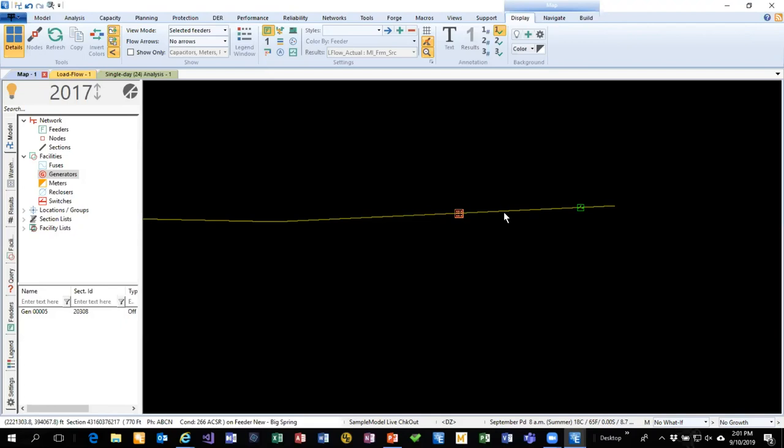I think at the secondary level, the load modelling that we've done at MV has been proved to be quite good and representative. I think it's because of the granularity and the unpredictability of the usage by individual customers. It becomes a lot more difficult to ensure that you have an accurate representation of what's actually happening at any one time. So you should see a lot more variation, even day-to-day on a secondary, compared to what you would see at the MV level.